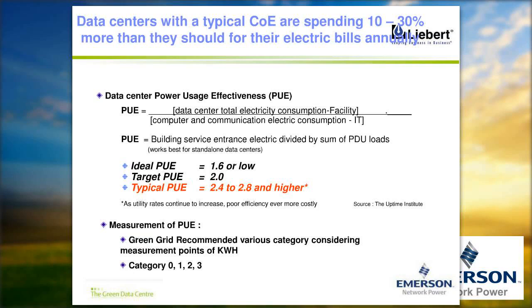Now, I am coming to the measurement of the PUE metric, which was developed by Green Grid, and is categorized as category 0, category 1, category 2 and 3. These categories are built up based on the measurement points of kilowatt hour. Green Grid strongly promotes the point at which you measure the kilowatt hour. Most Indian customers feel that their PUE is best, because probably it has been calculated on an instantaneous basis. But in real terms, it has to be calculated over a 1 year span, which covers all the seasons and all the types of ambient scenarios. And that's how it has to be measured in kilowatt hour.